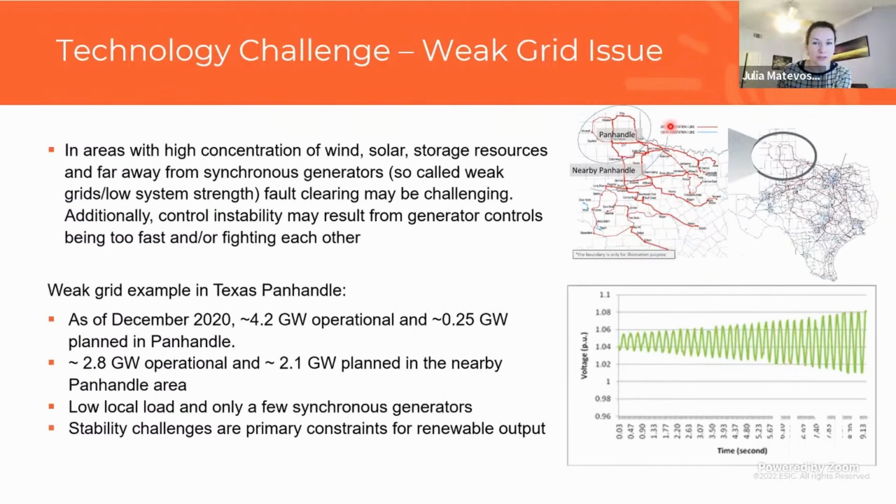So what it means is, see here, there is this line, maybe around Panhandle, there is this circle, right? And it crosses all these lines that are going out of Panhandle. And so they say, well, if I transfer more than a given amount on these lines, it means that this megawatt amount is being produced here. There's very little consumption, so all of it is flowing out. And if I have this many megawatts produced here, I see these problems.